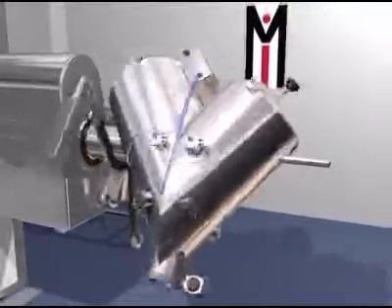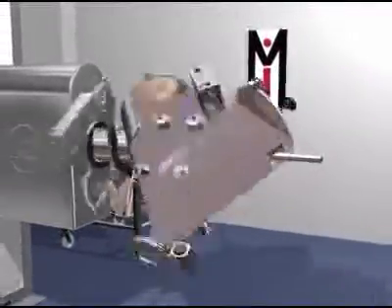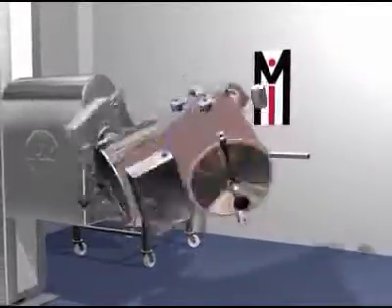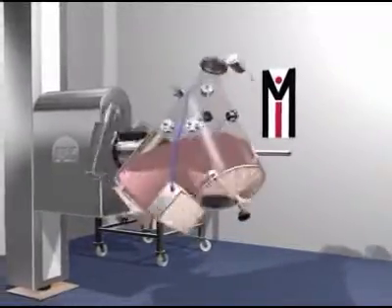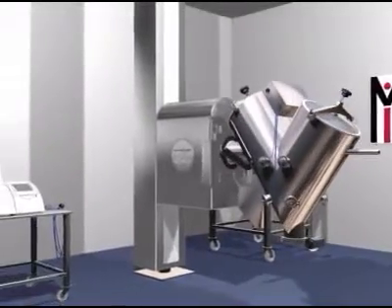At the onset of blending, the sensors are in contact with different materials. These feel different to the sensors, indicating non-uniformity. As blending occurs, the powder increases in uniformity. Measurements from the various sensor locations are compared during blending until the results converge and the powder feels uniform.